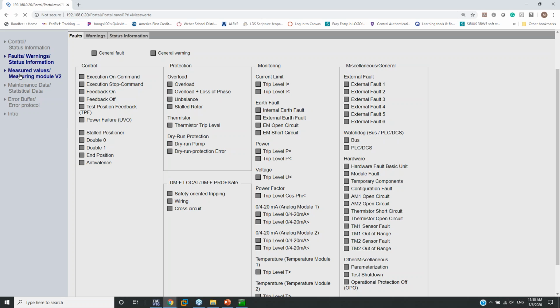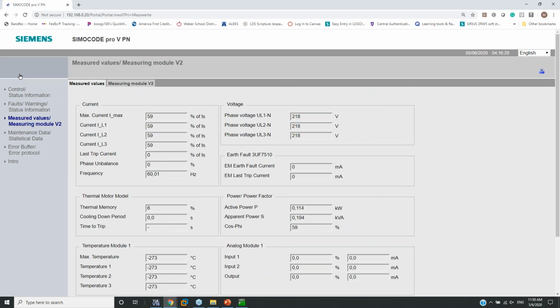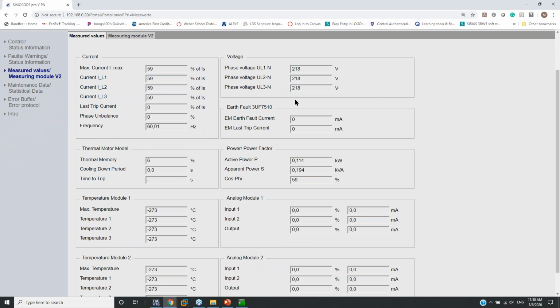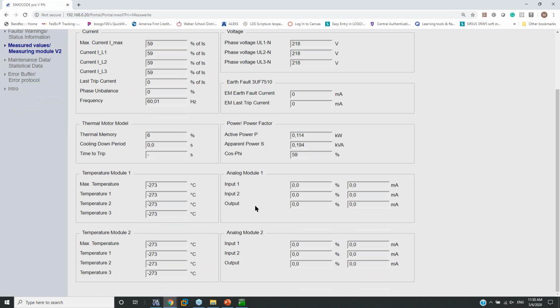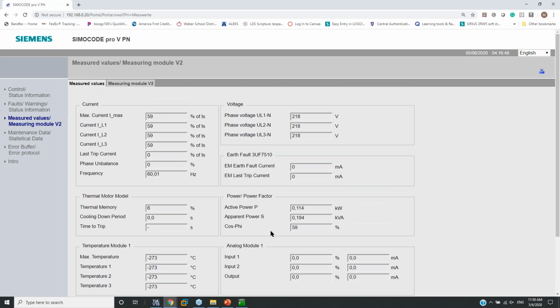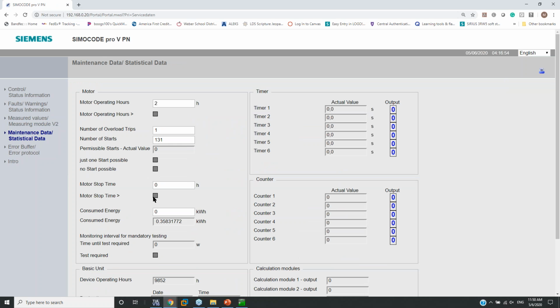Measured values. Here's the measured values of SIMOCODE. Okay, here's my voltage, here's my current, here's my kilowatt per hour, or my kilowatt, my kVA. Okay, if I had temperature modules, this would be reading those temperatures. My analog inputs, I don't have anything. Here's my maintenance and statistical data. Here's some key performance indicators of my motor.